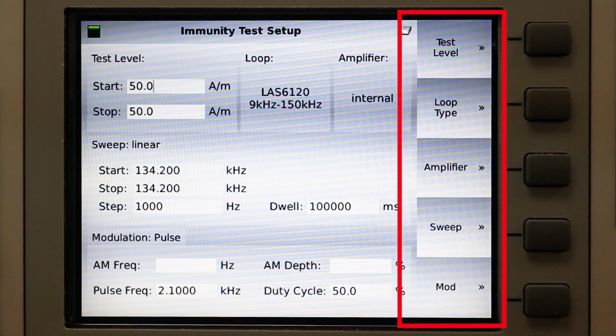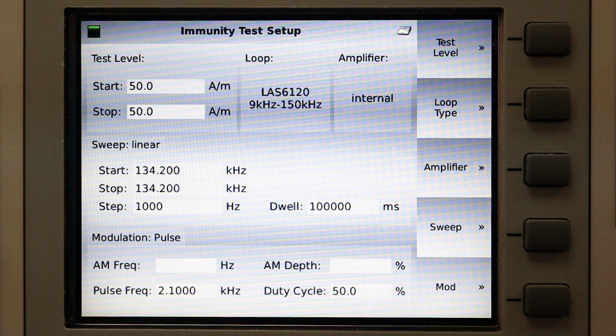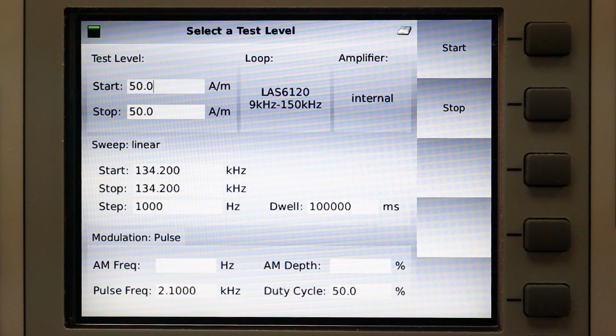This is where the test level, corresponding loop antenna, as well as other criteria can be changed. Let's start with our test level. Let's change that from 50 amps per meter to 65 amps per meter. To do that, hit the top button, the F1 button for test level, and let's start with our start. You can see right now in the test level section, we have our 50 amps per meter indicated. We want to change that to 65. So enter 65 on the keypad and then hit the enter button. We'll do the same thing for stop, 65, and then enter. So we've just changed the test level.